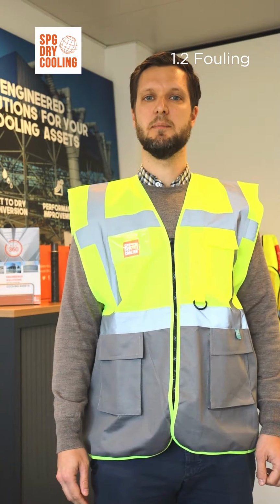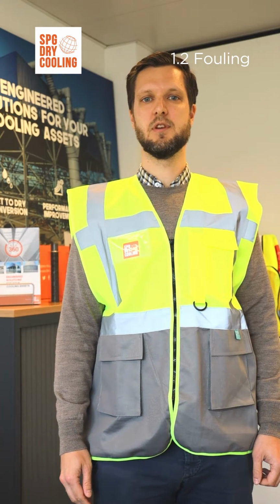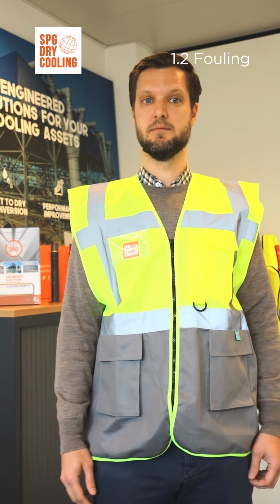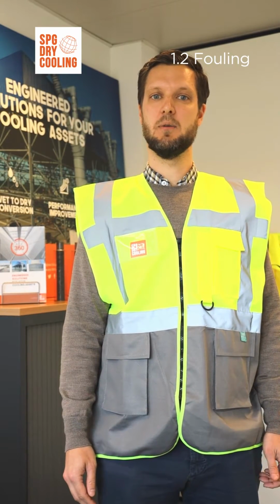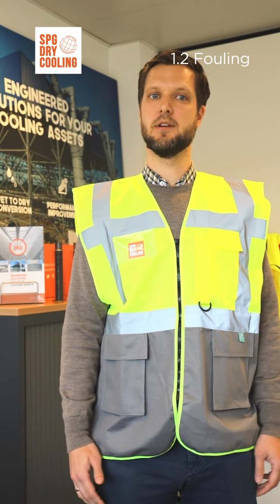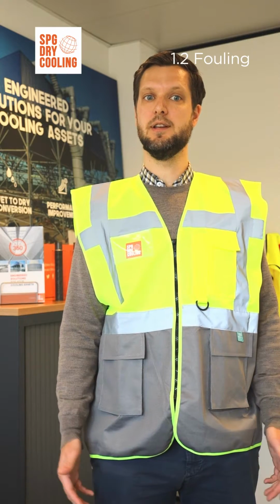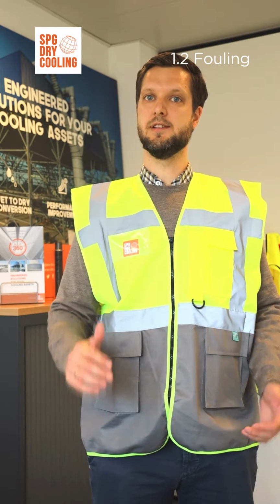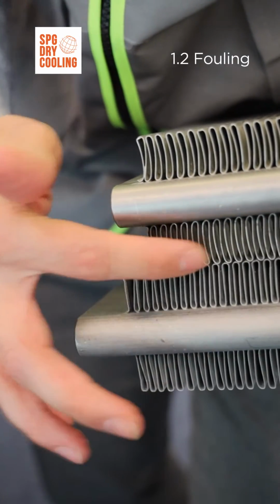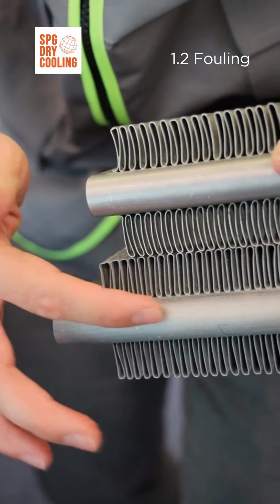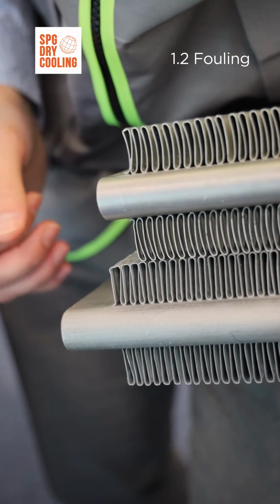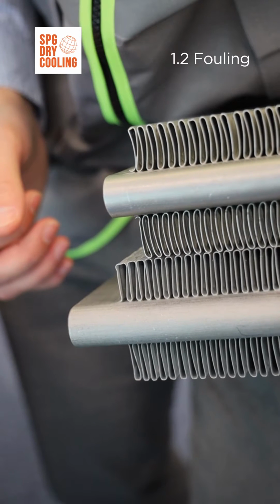Today we're going to talk about the concept of fouling. For some of you, it sounds familiar. Fouling is caused by dirt and other particles that attach themselves to the heat exchanger surface of the ACC. This layer reduces the heat transfer between the hot and cold media, directly decreasing the efficiency of your ACC. Dirt layers are reducing the cooling effect of the ACC, directly impacting plant performance.